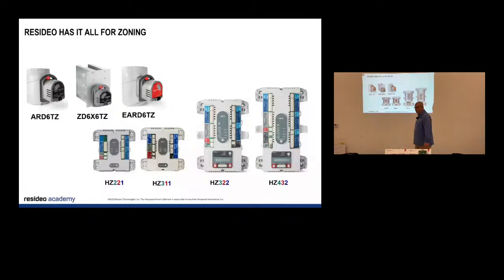But if you follow some simple rules that we'll go through, you won't have problems. And the biggest problem with zoning is noise. Noise, noise, noise. And the homeowner's number 1 complaint is noise all the time. So if you do it right, you'll never have noise. The other rule of thumb, you're not gonna have this really in any brochure. If you take the total CFM, so let's say I've got a 5-ton system, I've got 2,000 CFM, and that is what I would need for the entire house, but I only need for the master suite maybe 600 CFM.